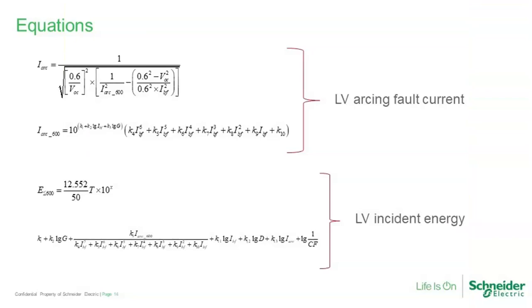Just to give you an idea of what some of the equations look like, here's a sampling from the latest version of that standard, IEEE Standard 1584, published in 2018. The equations on the top allow you to calculate the arcing fault current level based on the maximum fault current from your short circuit study, and then based on the clearing time of the circuit breaker, fuse, or relay in the system, you can plug in a few other factors into the equations on the bottom and calculate the incident energy, the amount of heat that the worker is going to be exposed to.